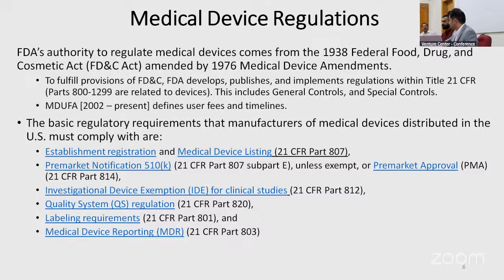Because when you look at the regulation, it will tell you a lot about your device, the risk types, as well as maybe even guidance documents that are relevant to you, or recognized standards that are relevant to you, or any special controls. So you want to be intimately familiar with your regulation for your device class. And there's also MDUFA, the Medical Device User Fee Amendment. This was introduced in 2002, and it renews every 5 years. This is the act which allows FDA to charge you a fee.